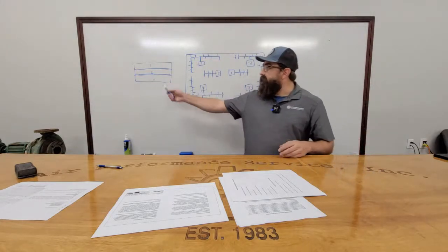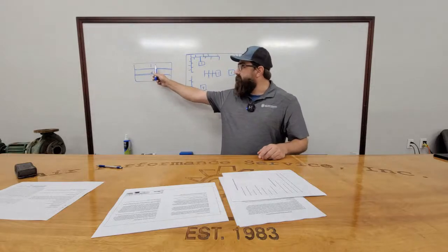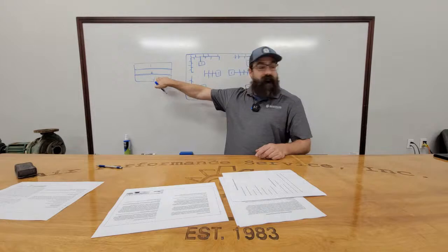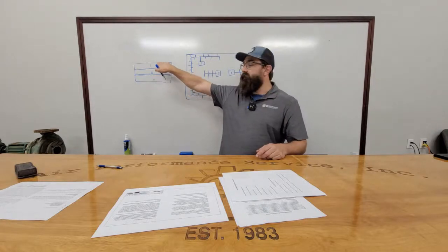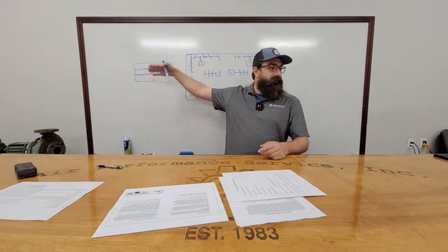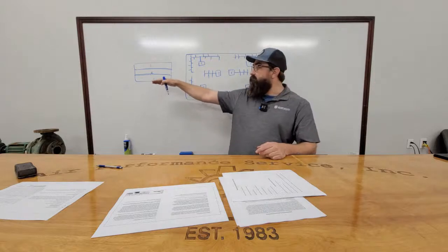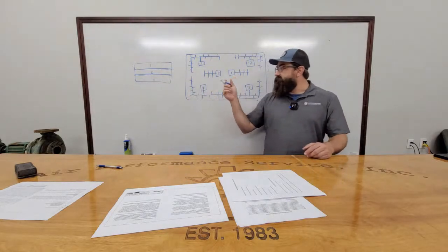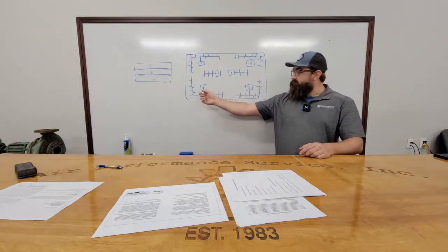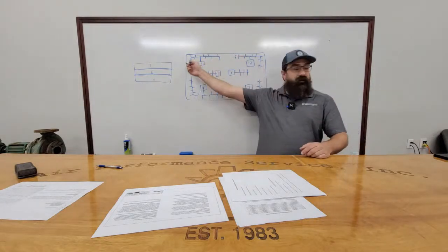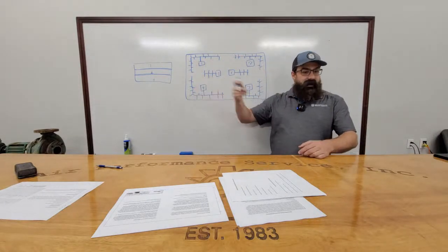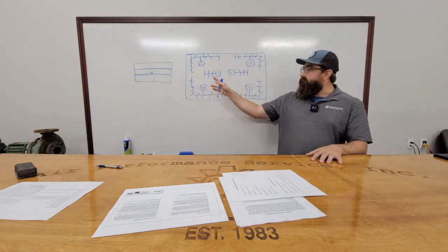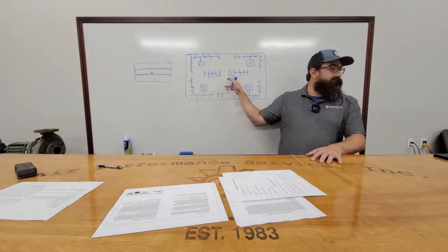So we start with our highest load, and then in the winter, we flip it based on outside air temperature. We would start the first floor first, then the second floor, then the third floor, because it's cold: cold drops, hot rises. Then on the floors, we stage the floors up too. We would stage the perimeter up first to create an envelope around the building, and then as time goes on, we would bring the interiors on.